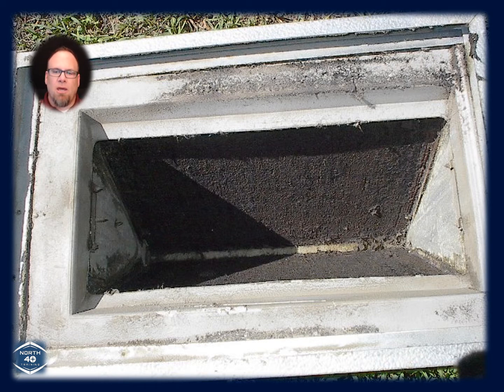So what they did is they go out there and they strap up the plenum with wire, so that way it stays in place as they pull out the furnace underneath. And rather than just stick your head under there and look up to see whether or not that coil has stuff that you could clean out of it while it's now wide open, they didn't do that. They got ahead of themselves and moved much more quickly than what they should. And instead of finding this mess, what they actually did is just shove the new furnace under there, left that coil where it is, didn't check it out, built the plenum down to the top of the furnace, and then ran the furnace. Couldn't figure out why it tripped limit.